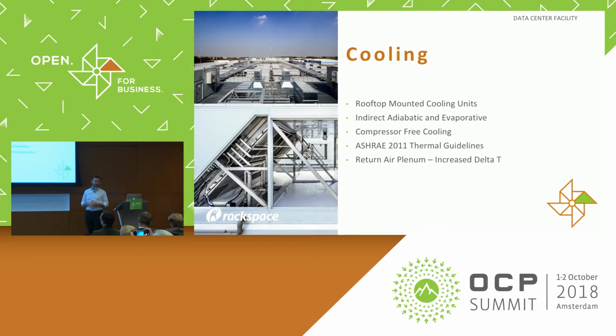One of the most impactful design changes that we made from a traditional data center is the use of the adiabatic and evaporative indirect air cooling units. They're mounted on the roof. The alignment of the design set points to the ASHRAE 2011 thermal guidelines is what allowed us to use these units. And with that, we were able to eliminate the compressors, saving a lot of energy overall. The use of hot aisle containment, as mentioned before, allows the air to return to the air units with the return air plenum. And this provides an increased delta T back to the cooling unit, which increases the capacity and efficiency of that heat exchange.